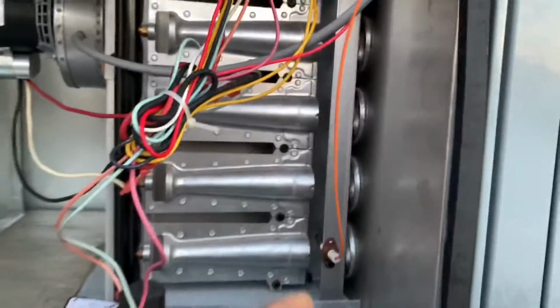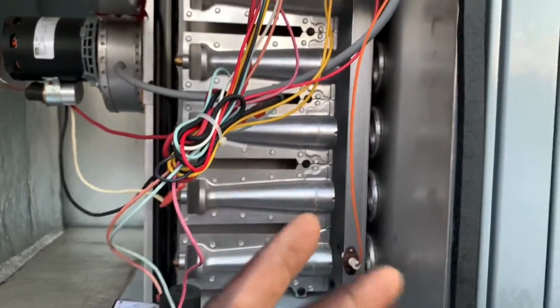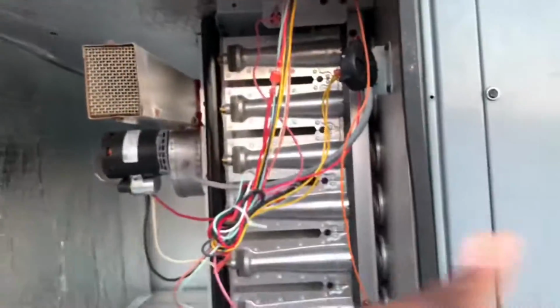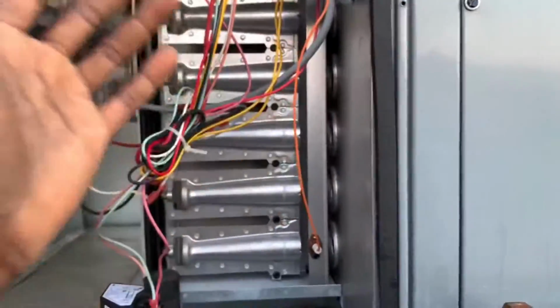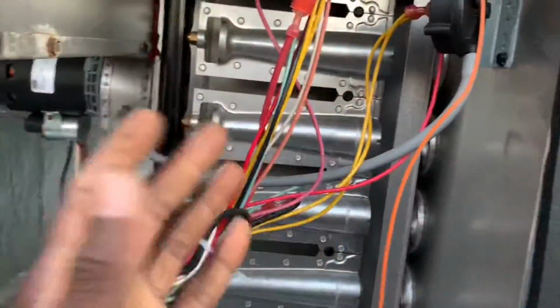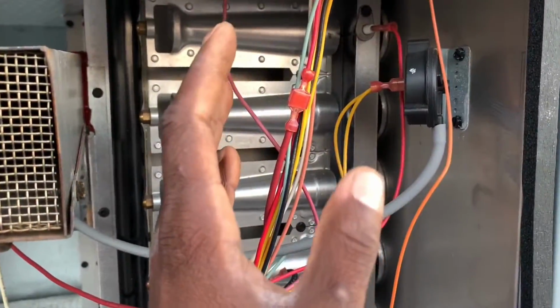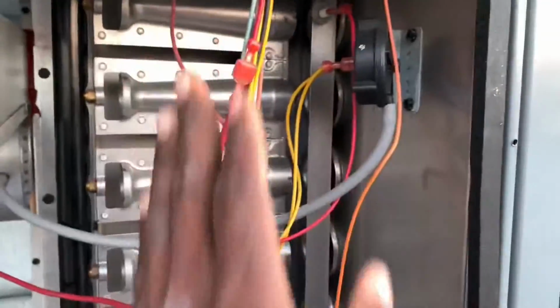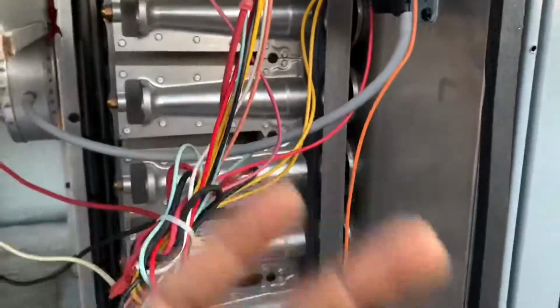So that means the heat exchanger is cracked. And if it's cracked, the supply fan, the air that blows from the vent, is going to interfere with the flow of gas through the heat exchanger, and you're going to have flame rollout. So hence the reason why you need to call a pro. All right, so that's the flame rollout, and here's your flame sensor.